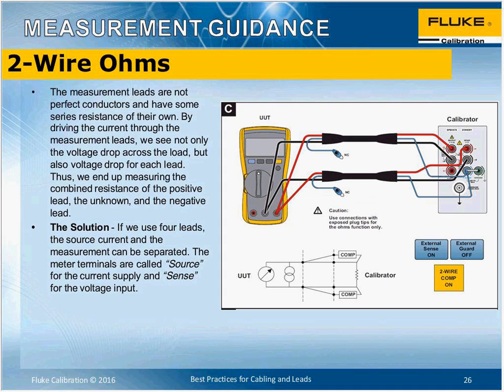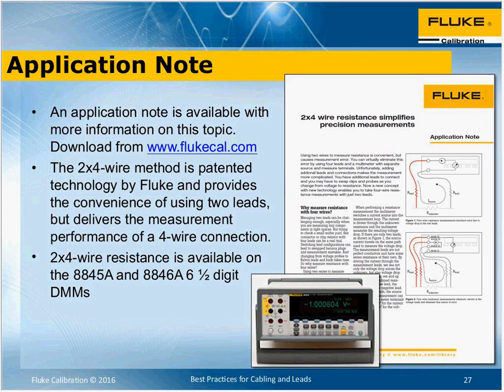When there is not a 4-wire method available, this method allows you to use jacks on the DMM as shown there, but you have 4 connections at the calibrator. This is a mode that you have to turn on in our calibrators, but effectively it's the same principle as the 4-wire method. Application note, as I mentioned, I'll be sending that along with this webinar.